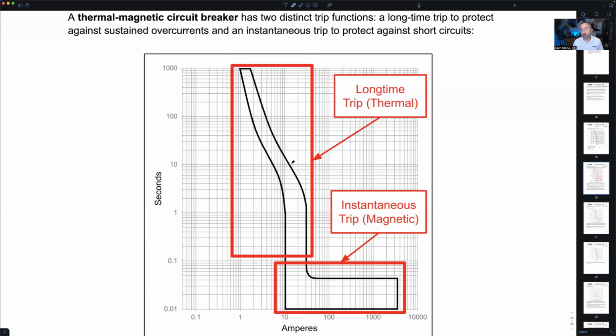So for me, the most common ones I've worked around are motors, MCPs, motor circuit protectors, breakers built specifically for motors. In fact, I've got a three-phase Cutler-Hammer one right off my right shoulder. I don't know if you can see it. Those are typically always going to be a thermal mag breaker.